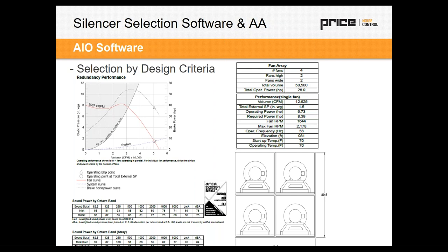And I need a silencer that brings the sound power that you see in front of you of 92 dBA single rating down to about 30 points. So you still don't have a lot of the details. It's at the design stage, but they are saying, hey, I need a silencer that gets me to 60 dBA max. So now it's by design criteria, right? dBA is a rating that you use outdoors. You have 50,500 CFM.